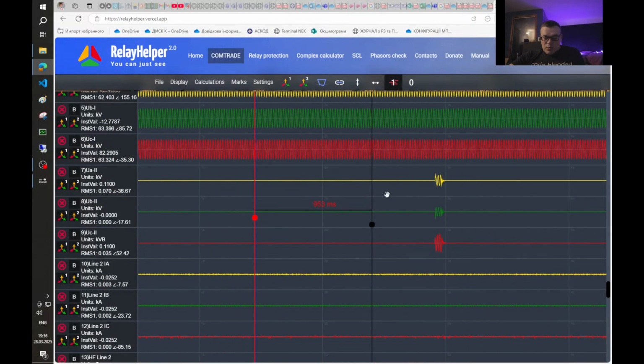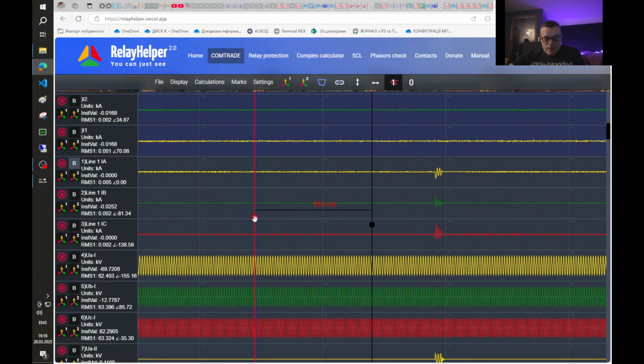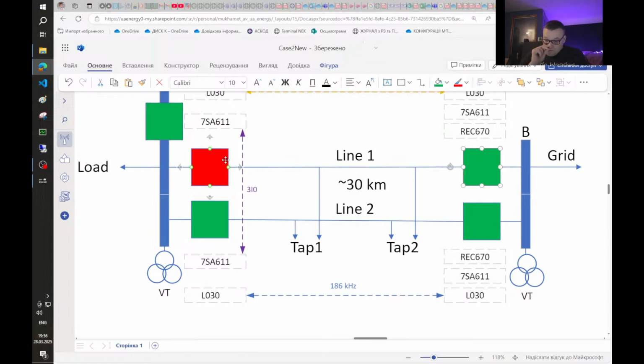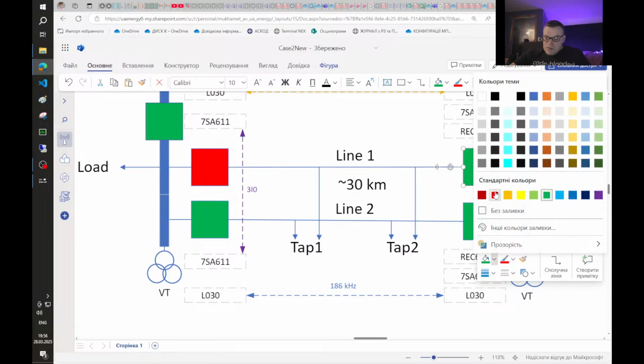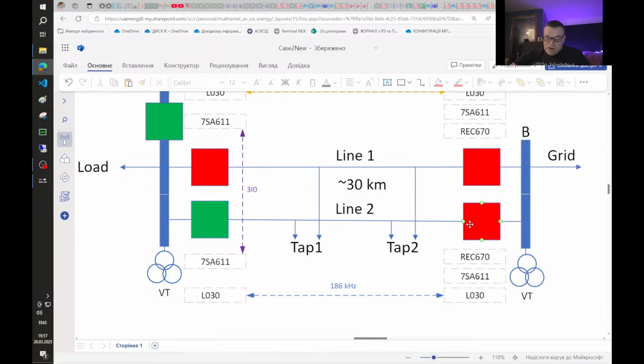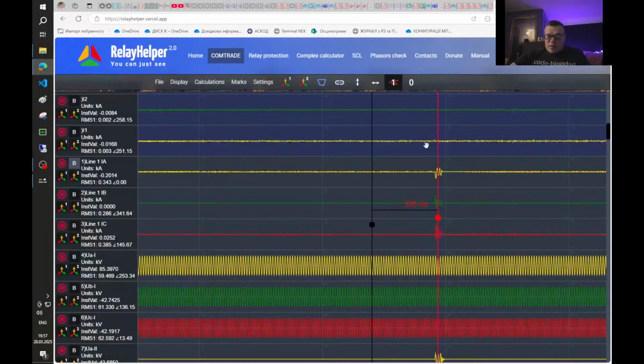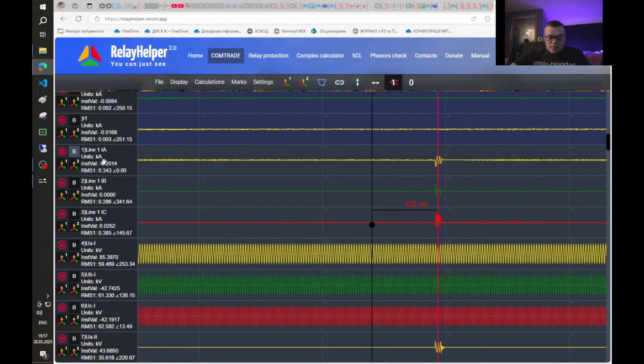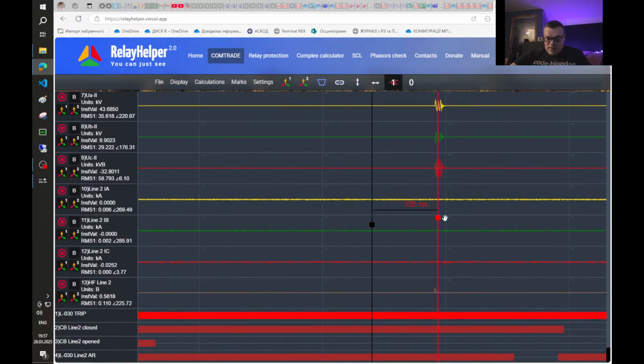Then we can see that's why we can see current that goes through the first line when there was AR from substation B, because this circuit breaker was not tripped. So in the period of time of AR, we can see this condition. This circuit breaker was closed by AR at the same time, and this circuit breaker was opened. So that's why we only see currents on line A and don't see any currents on line B.